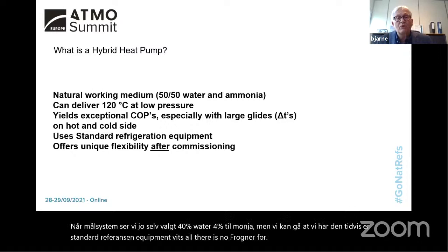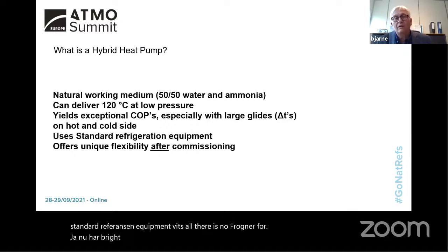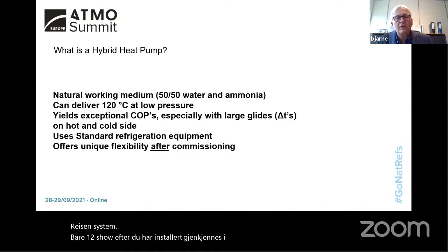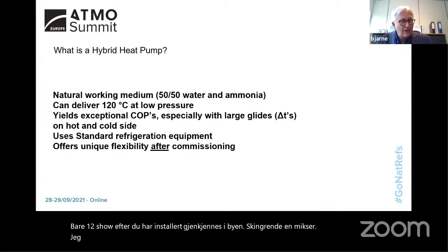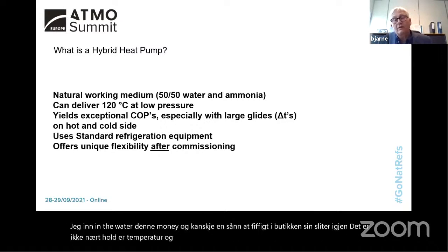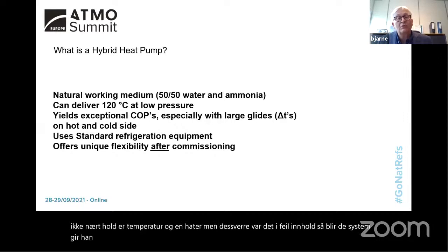And when you have a good temperature glide on the hot and cold side, we get extremely good deltas or COPs. Like I said, it's a standard refrigeration system, but after you've installed it, you can change it by adjusting the mixture rate of water and ammonia. You can change it from 50-50 slightly, and then adapt to either colder temperatures or even hotter than the design 95.